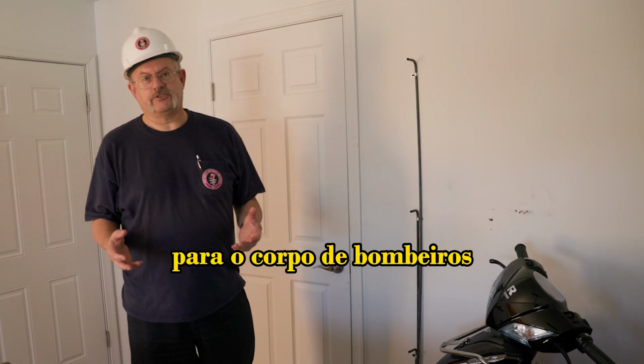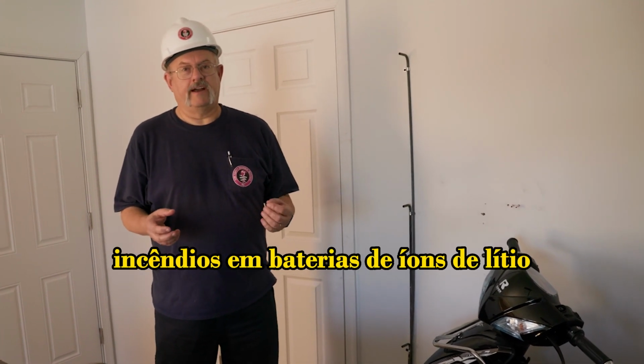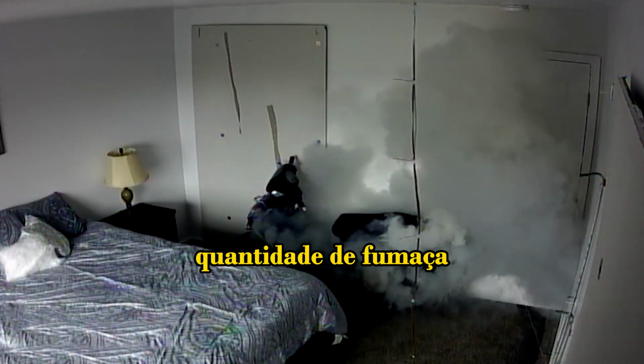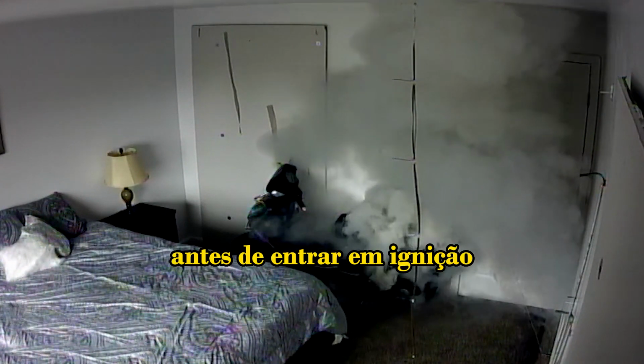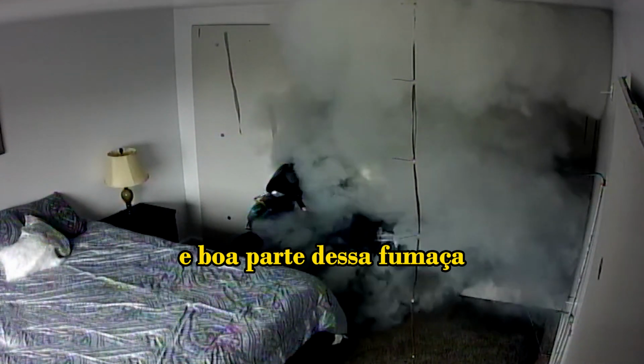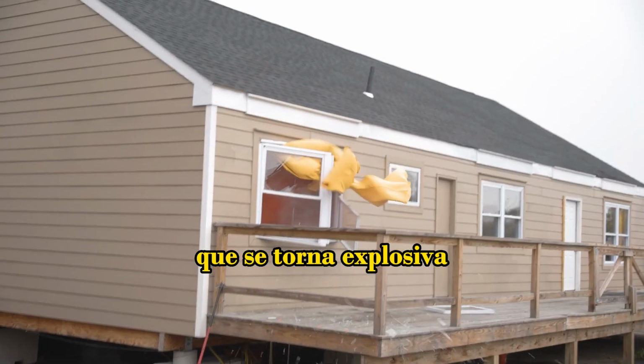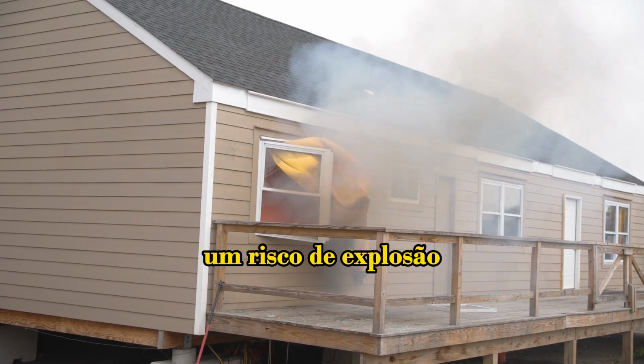In terms of challenges for the fire service, lithium-ion battery fires produce a tremendous amount of smoke in many cases before they ignite. Much of the smoke is flammable, or it could reach a concentration where it's actually explosive, so there could be an explosion hazard.